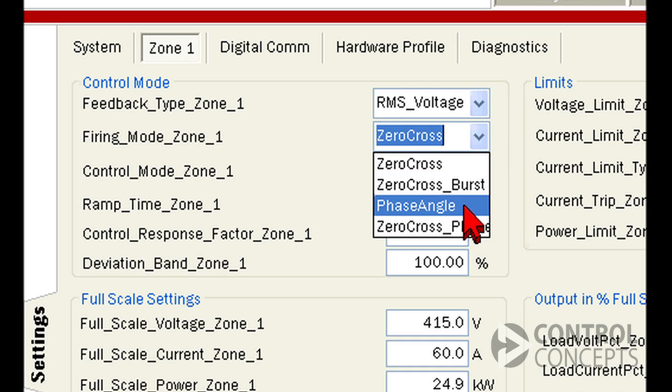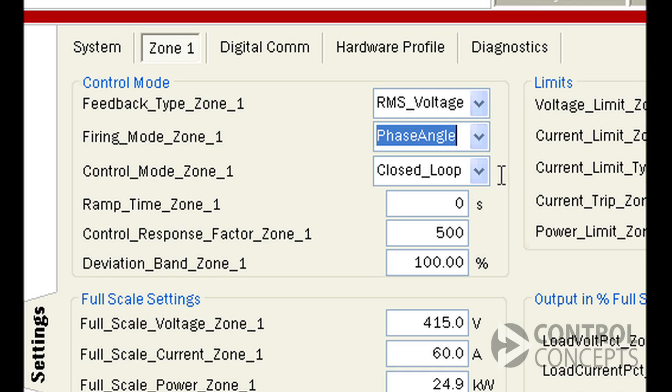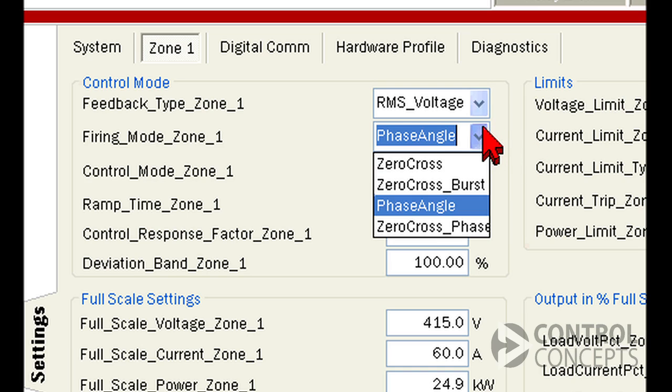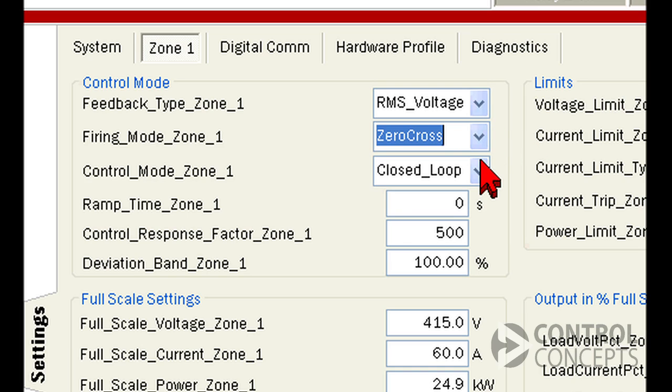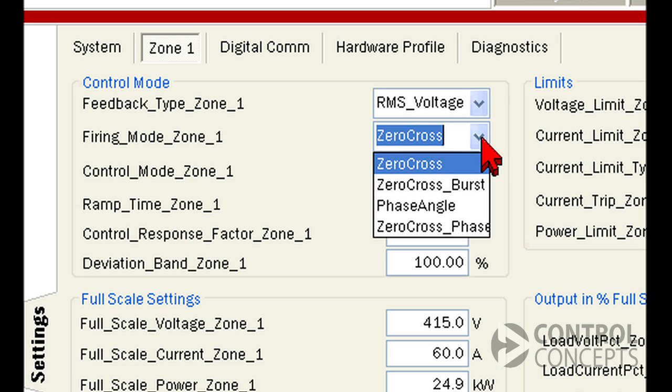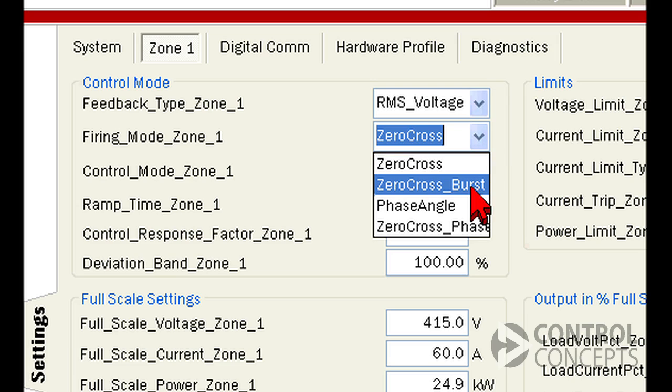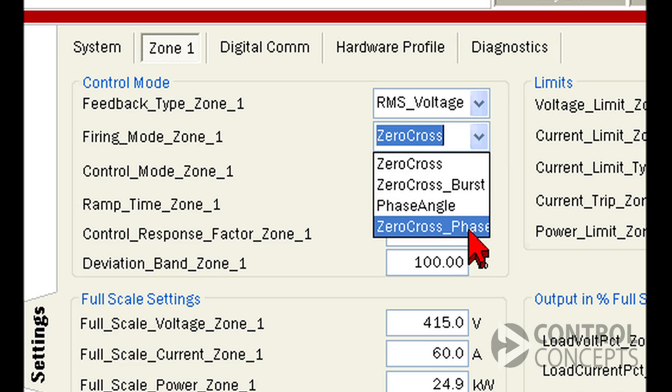Your firing mode will depend on your hardware. For transformer coupled or highly inductive loads, or loads with a precision temperature control requirement, we generally recommend phase angle. Otherwise, we recommend zero cross. The advanced modes, like zero cross burst and zero cross phase angle start, are used in situations that call for extreme power efficiency. Consult Control Concepts for more information about advanced modes.